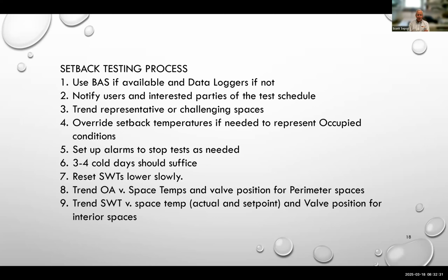Reset the supply water temperatures slowly so you can see the response. Trend outside air versus space temperatures and valve position for perimeter spaces. Trend supply water temperatures and space temperatures, actual versus set point, and the valve positions for interior spaces. This testing process is also useful as a standalone retro commissioning exercise, even if you don't proceed with a conversion. You can identify problems you have or weak elements in your system.